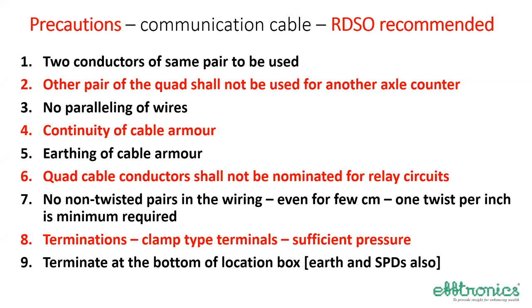Wires shall not be paralleled. See, after the cable is out, the cables are terminated at the cable termination rack, and then from there we extend it to the equipment. There we have to lay tail cables. There we have to be really careful. And paralleling of these wires with other wires can cause induction. Then continuity of cable armor is very, very important. Why it is important, we will see a little later. And earthing of cable armor also, these two.